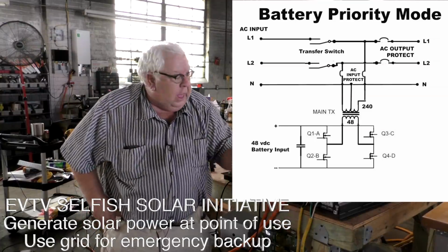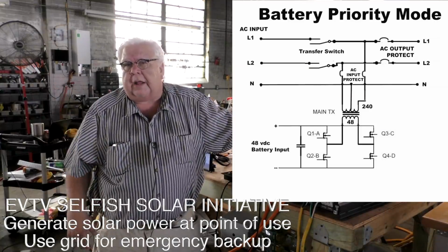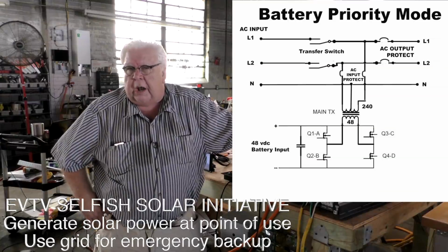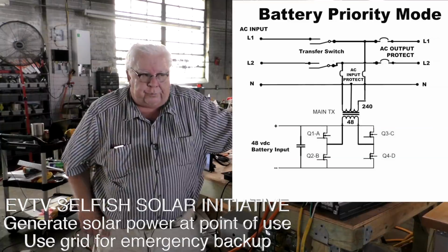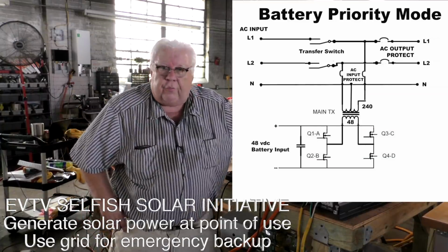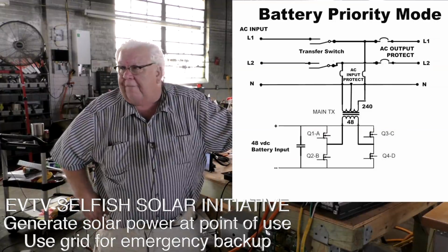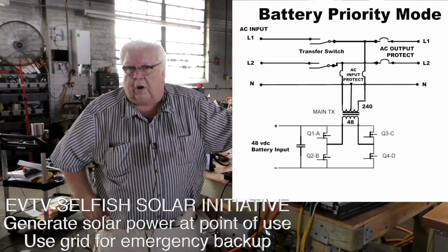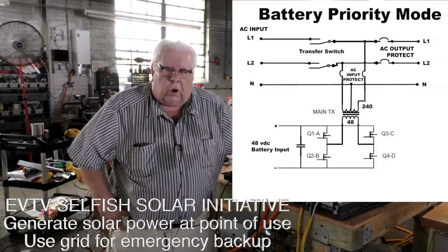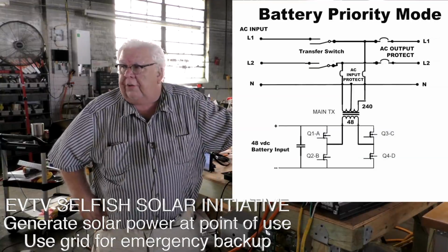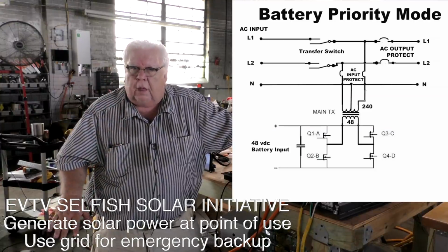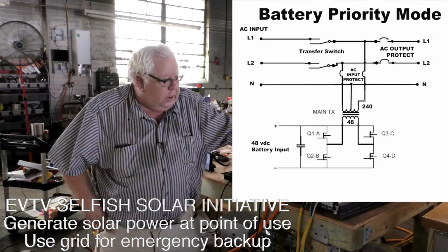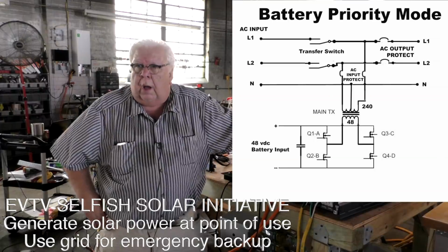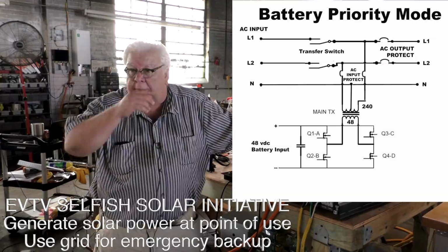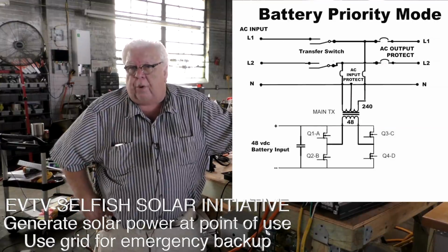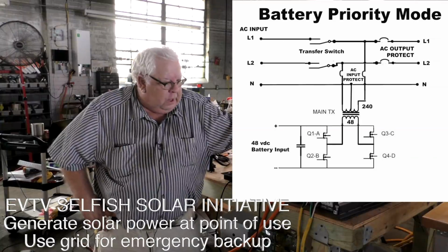You can have an AC input, and an internal transfer switch simply leaves the AC not connected until you get down to the 39 volts DC, at which point it kicks in the AC. The AC then is passed through to the loads, but it also charges the battery at about 5 kilowatts, about 120 amps. So in normal operation, you would work off the battery, charge the battery from solar, and use the AC output. But in the case that it got down too low, you don't need a separate charger hooked up to the grid. You can simply hook the grid into this, and it will charge the batteries back up to full, and then switch back to battery priority mode. And so that's quite a trick.